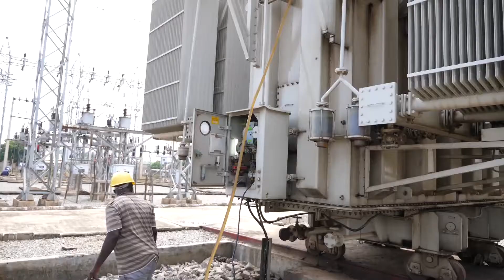The two transformers have different feeders. Like T1 has 3 feeders: K1, K2, K3. Each of these feeders carries a load that depends on load demand. K1 can carry up to 18 megawatts. K2 can carry up to 18. The other one can carry up to 15. But as much as possible, we try not to exceed the capacity of the transformer. So at times, if the load goes high, we have to drop some load, or we take the decision to drop some of the feeders in order not to go beyond the capacity of that transformer.